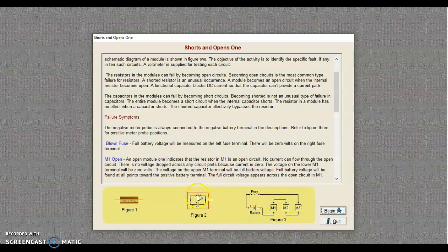Those modules consist of a series, I'm sorry, a parallel structured resistor and capacitor, and they are protected by a fuse that's in here. So potential problems, we could have a blown fuse, which is an open in this series circuit, and so we will see all the source voltage at that fuse area.